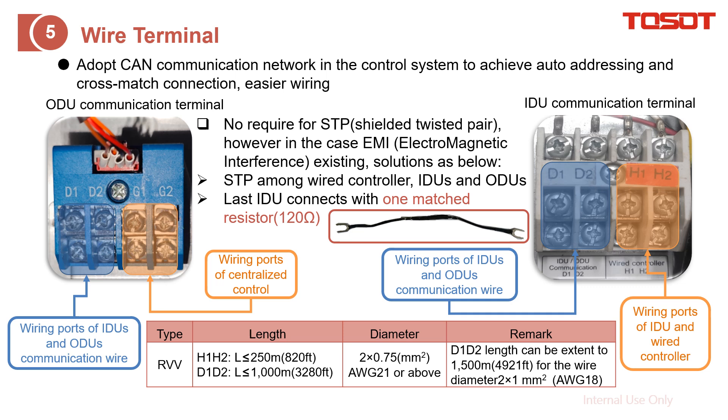Here is the detail on how to do the wiring. The system adopts CAN communication in the control system, which achieves auto-addressing. Your wiring cross-match is available, which means for D1-D2, you don't need to memorize the colors of the wire — you can just connect them freely. The same applies for H1-H2 and G1-G2: you don't need to memorize the color, just do the wiring.